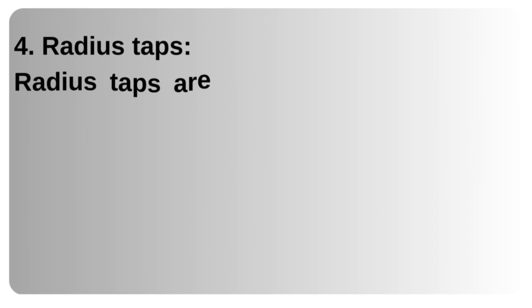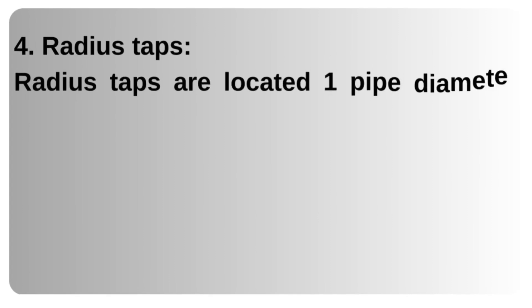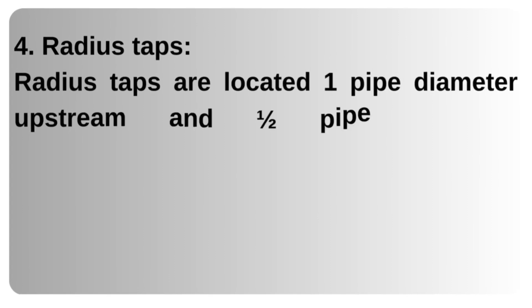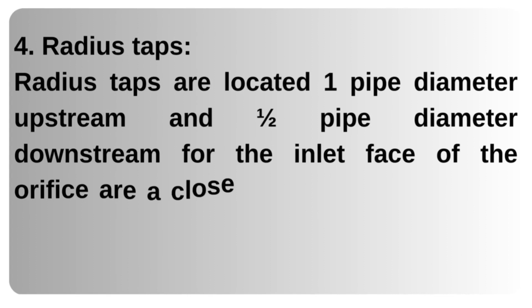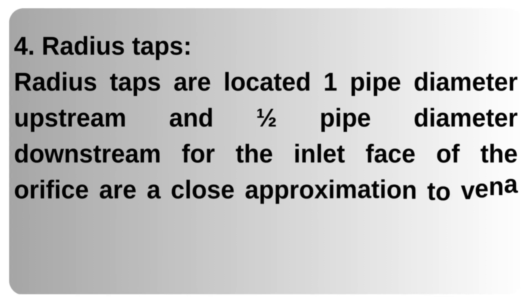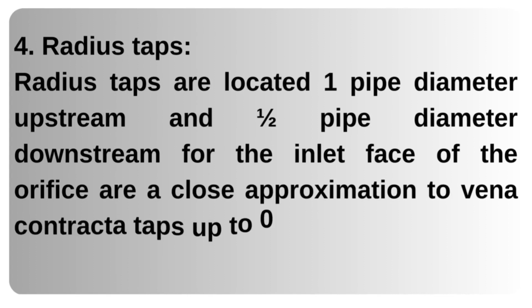4. Radius taps — located one pipe diameter upstream and a half pipe diameter downstream from the inlet face of the orifice. They are a close approximation to vena contracta taps up to 0.72 beta ratio.